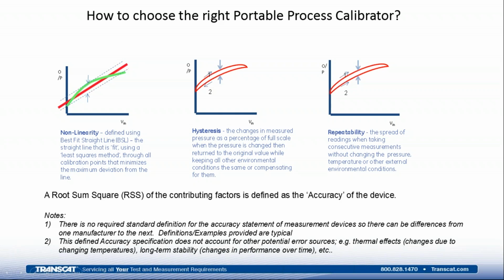And then repeatability, similar to hysteresis, is defined as the difference in output for a given input when repeated applications under the same conditions are made. So again, using our pressure sensor example or pressure gauge, if we apply pressure, release that pressure, apply pressure again under the same conditions, the difference in output would be the repeatability or non-repeatability of that particular device. So we take these three components and we root sum square the contributing factors, and this is defined as the accuracy of the device.